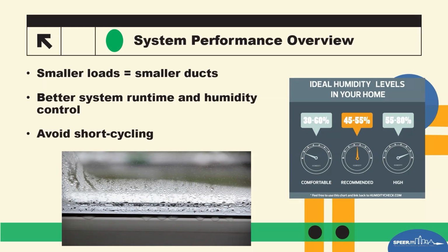They say basically the comfort level is 30 to 60, recommended is 45 to 55, and then high is anything 55 and above. And we've seen a lot of the foam encapsulated houses that have had a foot saw hole cut in the building. They're pushing that 80% or higher a lot of times, and the higher you get to the ceiling, the higher that humidity goes, and there will eventually be a condensation point that will happen just inside the envelope, which is usually right below the ceiling, and that's where you're going to start to get some mold problems built up.